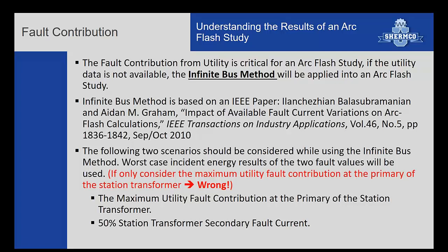So we'll talk a little bit, going back to this short circuit current versus arcing current. Over time, engineers have often used what's called infinite bus when doing short circuit studies. Infinite bus basically gives you the worst case for how much current could be seen on your system. That does not necessarily give you the worst case on what arc flash or incident energy a worker would see. So you can't use this infinite bus method alone to get the worst case.